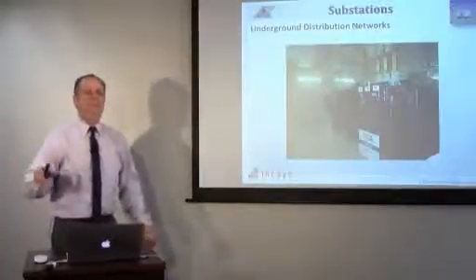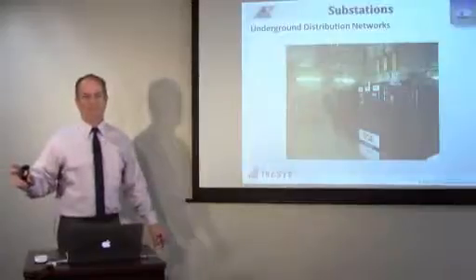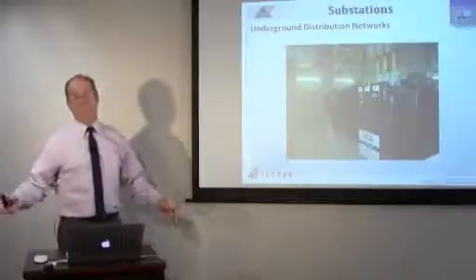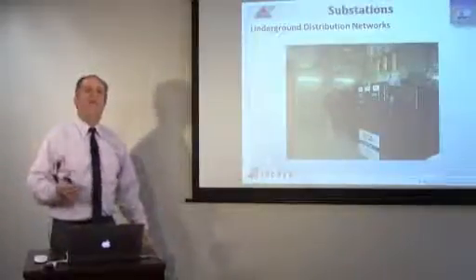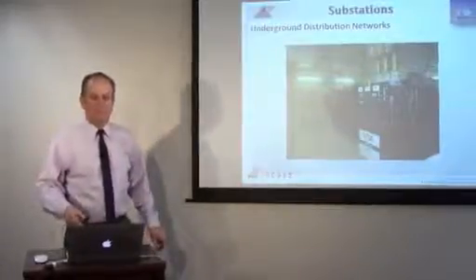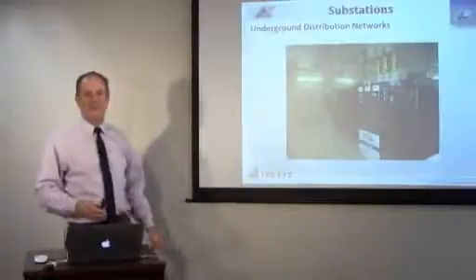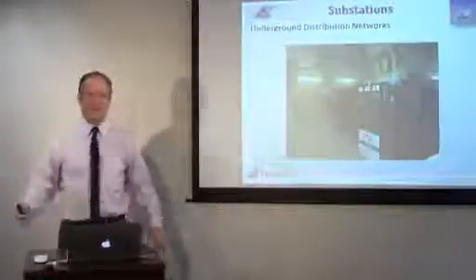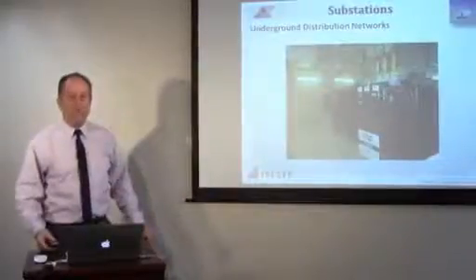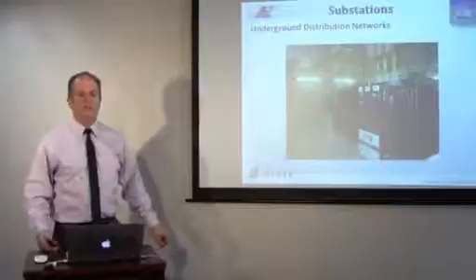And if there's a problem in there in the vault, it becomes very major. You have to trip all the transformers to stop it, or cut the cables or what have you to stop the arcing. Underground networks are designed for high reliability, so even if there is an arc, you still get good voltage at the other side of the city and things are still operating even though you have a big arc going on this side. So it's a different animal, and it's a whole subject in itself, talking about underground distribution networks.